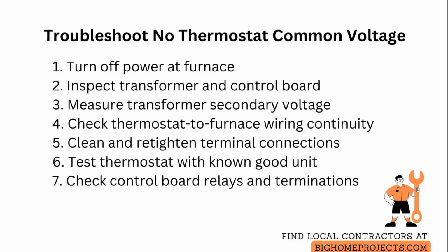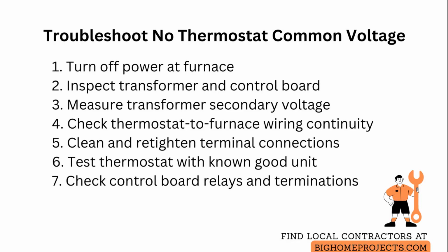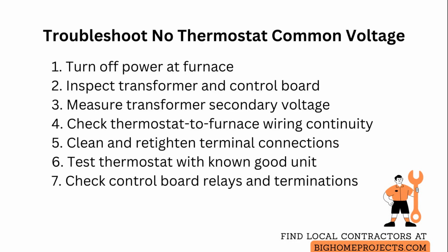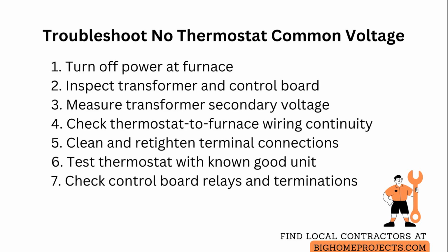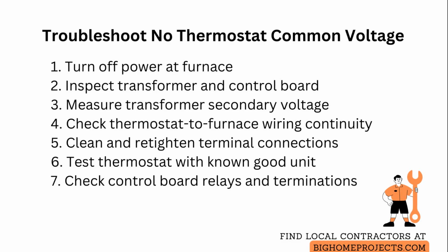If the transformer reads correctly, remove the thermostat from the wall and measure between the common terminal and the hot terminal at the thermostat cable bundle at the furnace to isolate whether the wiring carries the common. An open or shorted conductor between locations implies damaged or miswired cable.